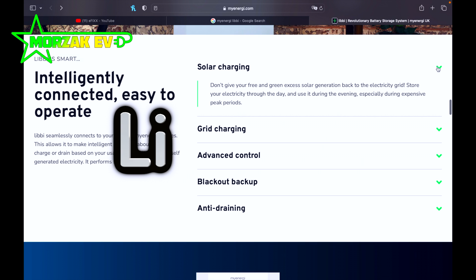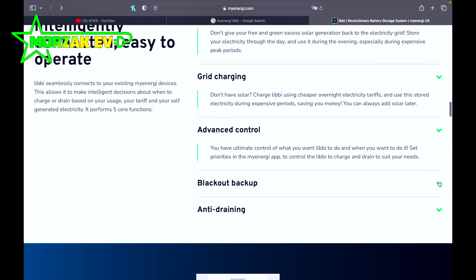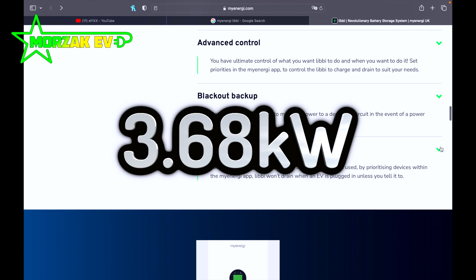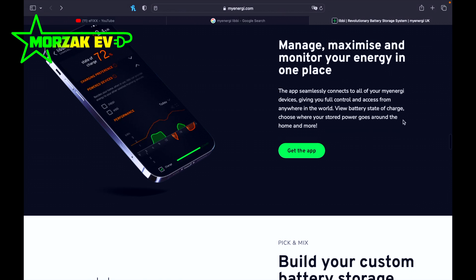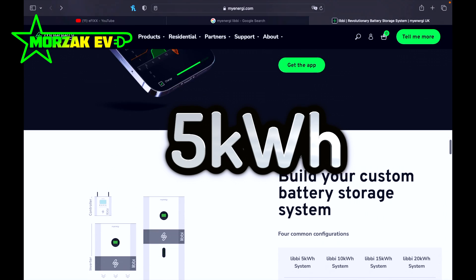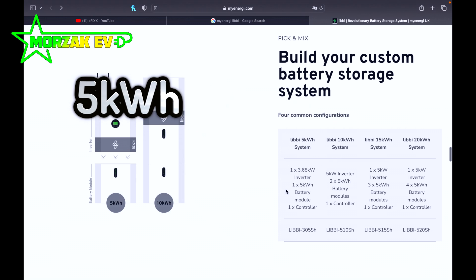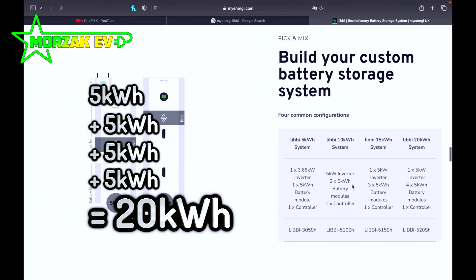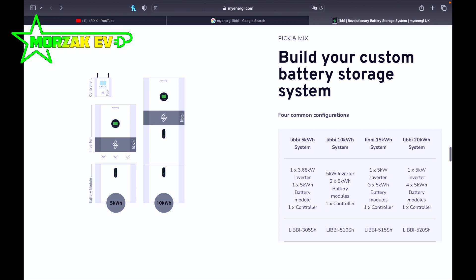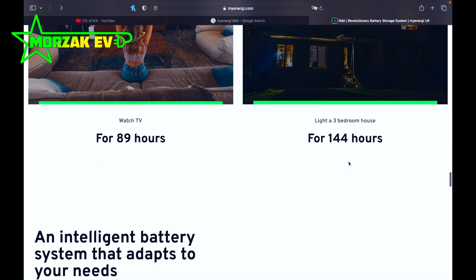The libbi itself is a lithium iron phosphate battery coupled with a hybrid inverter. The inverter is available in 3.68 kilowatts and 5 kilowatts. The battery is available in 5 kilowatt-hour modules and up to four modules can be coupled together, meaning you can have 5, 10, 15, or 20 kilowatt-hours of battery storage coupled to one inverter. You can also have multiple inverters according to myenergi, so the system is modular and can be expanded.